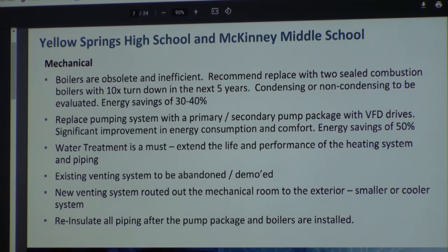And they both run at like 65%, so that neither of them is running as hard as it has to. When a boiler's running at full burn, it's inefficient - they're designed to run somewhere less than that, and that's their most efficient point.